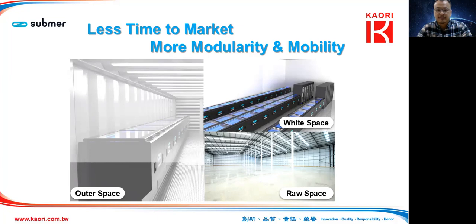All you need is electricity and piping for cooling, and also white space, which is more for the old data center using immersion cool technology. On the left, you can see outer space actually means you can have the immersion tank in a container, or a modular solution. Since the cooling is not related to environmental temperatures, you can have the tank inside a container but still have your IT running normally.